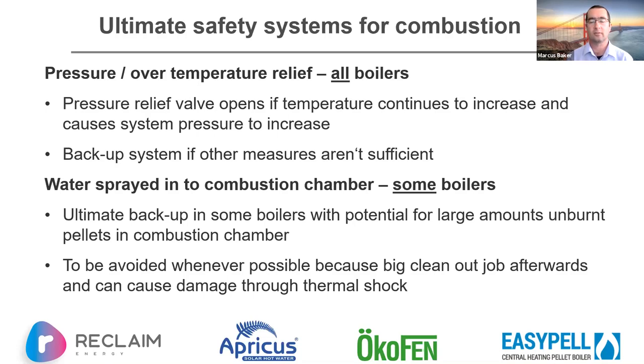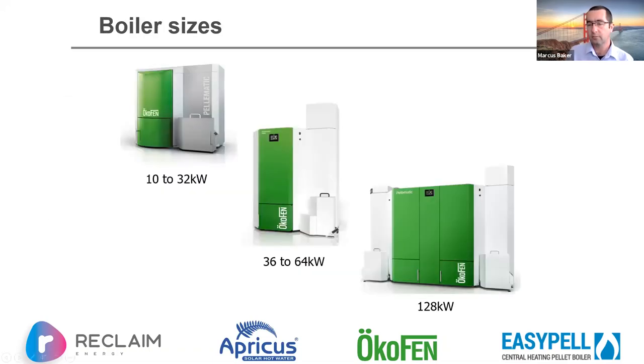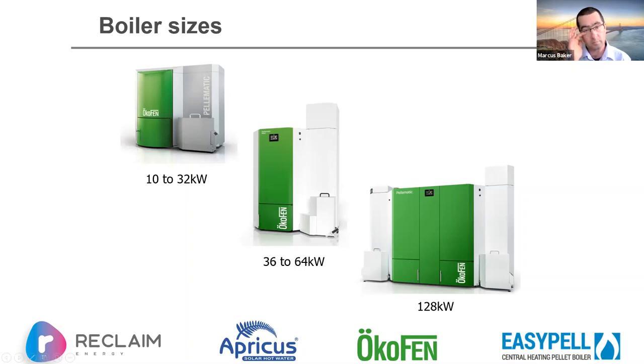The water spray emergency system is best avoided because there's a big cleanup job if water gets into pellets — they swell up, cause all sorts of problems, and you can have damage through thermal shock to the boiler. Looking at sizing — using the Ökofen example because it's most accessible, though all available boilers in New Zealand span a pretty similar range.